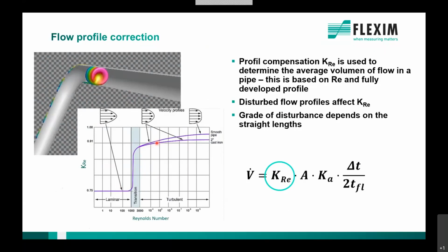and it is also influenced by the roughness of the pipe. When we have a disturbed flow profile, like a 90-degree elbow, as the top left picture shows here, our assumed flow profile for an undisturbed axial symmetric flow is not the case anymore because of the disturbance caused, for example, by the 90-degree elbow. In that case, our K Reynolds has an error, and the disturbance correction basically compensates that error. That's what we do here with our automatic disturbance correction. We compensate the error of known flow disturbances. And the grade of the disturbance depends on the straight length, right? When we have enough straight lengths, we have a fully developed flow profile again. If we do not have enough straight lengths, then we have to deal with a disturbed flow profile.